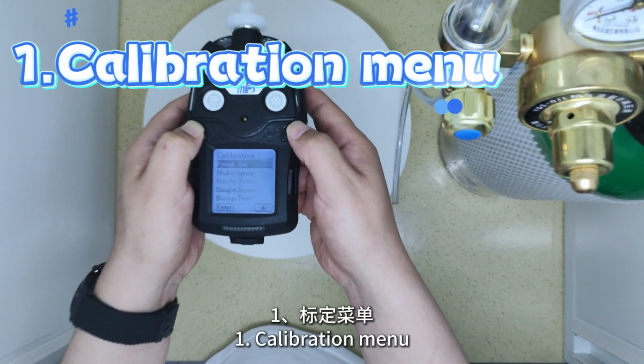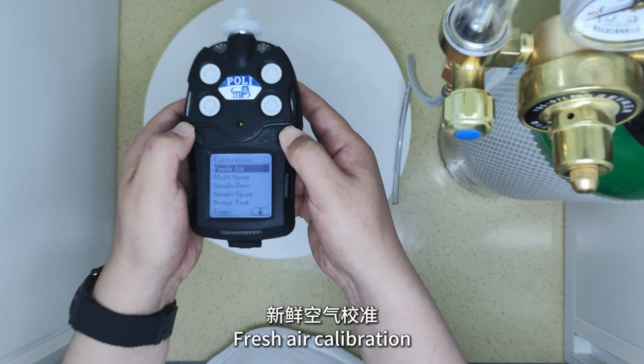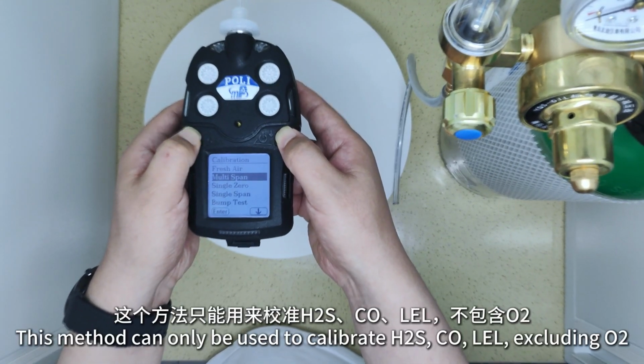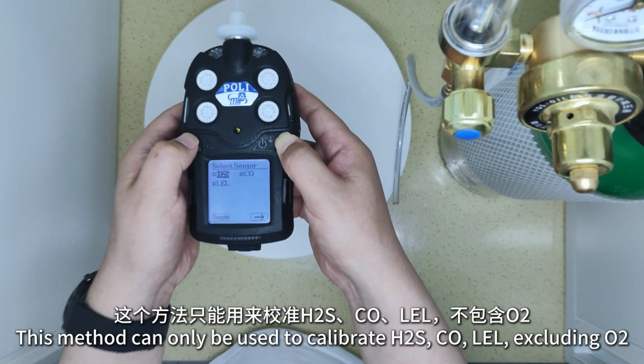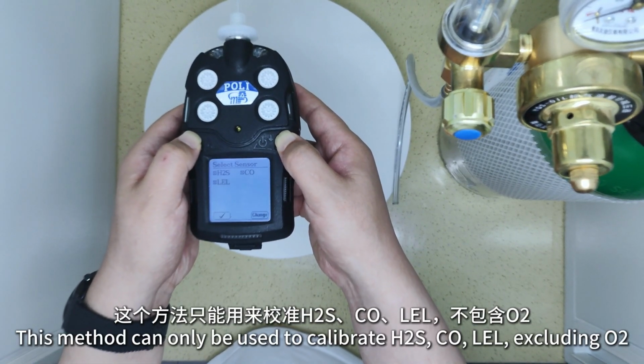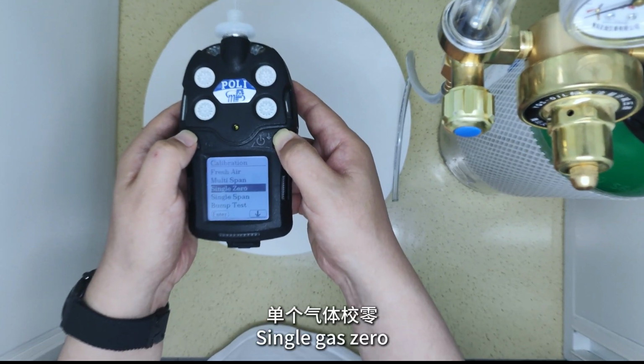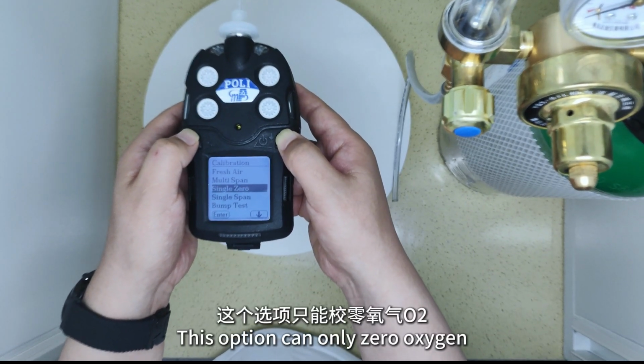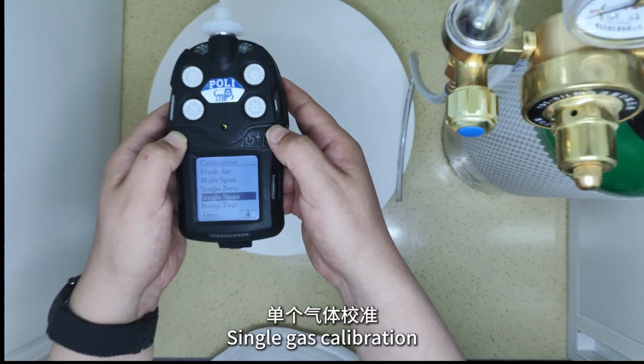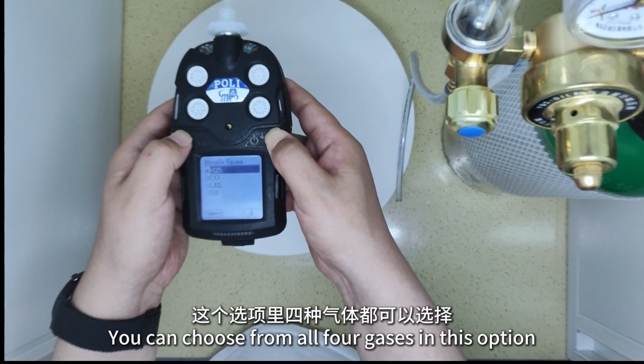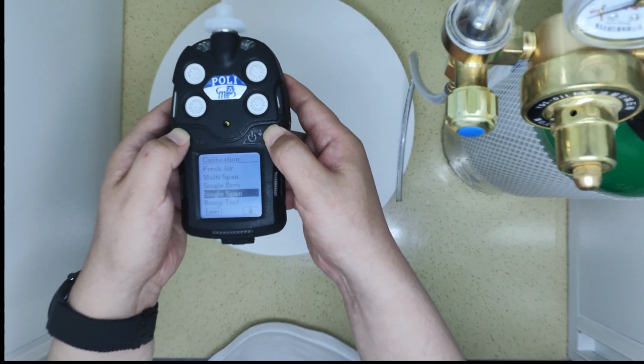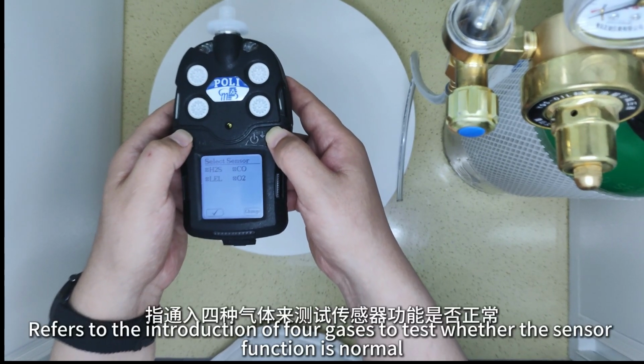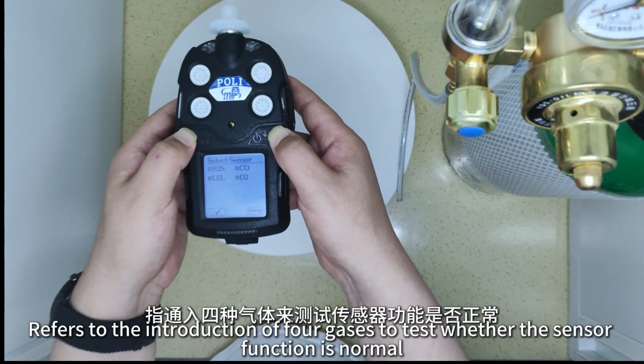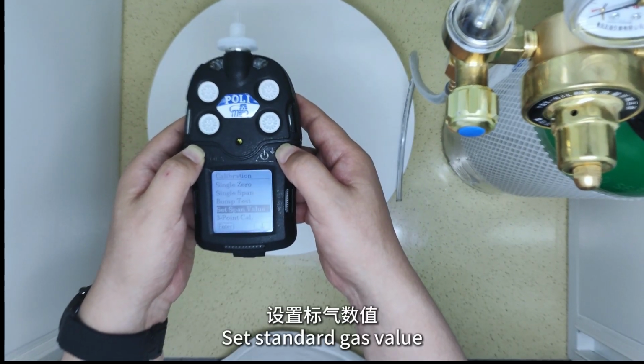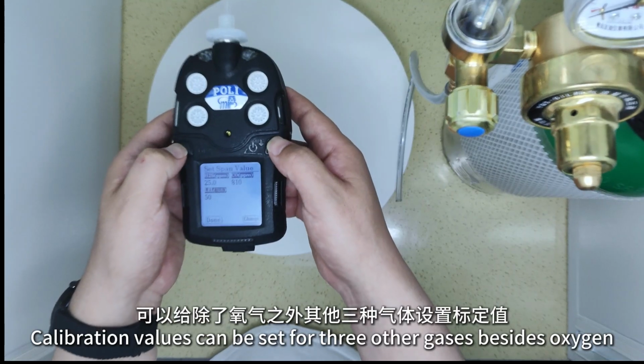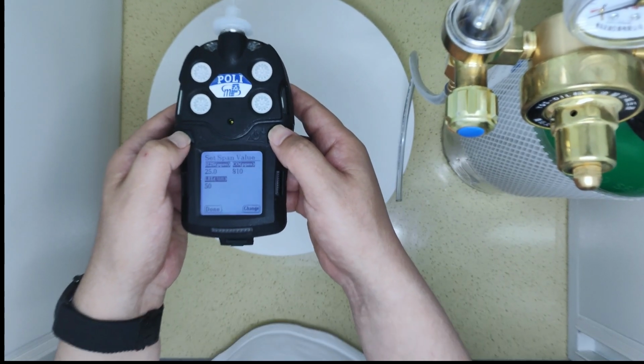1. Calibration menu. Fresh air calibration. Multi-gas calibration. This method can only be used to calibrate H2S, CO, LEL, excluding O2. Single gas zero. This option can only zero oxygen. Single gas calibration. You can choose from all 4 gases in this option. Bump test refers to introducing 4 gases to test whether the sensor function is normal. Set standard gas value. Calibration values can be set for the 3 gases besides oxygen.